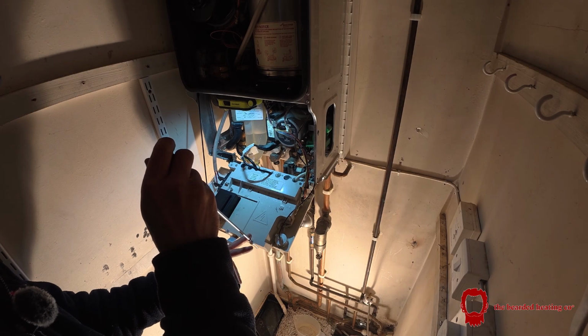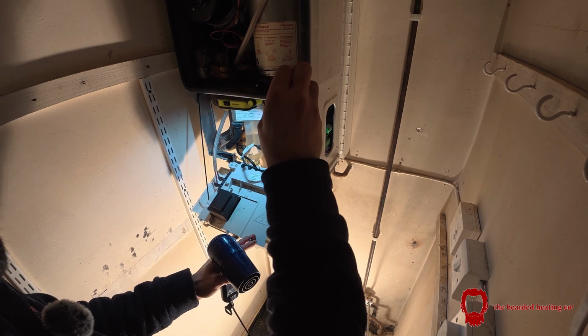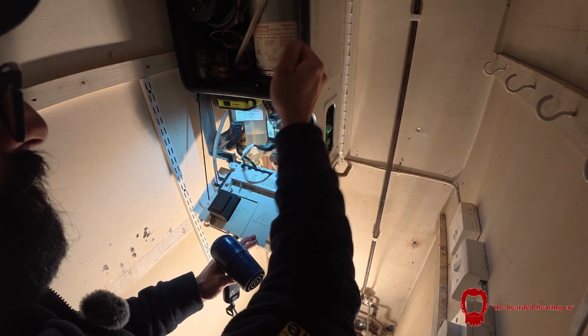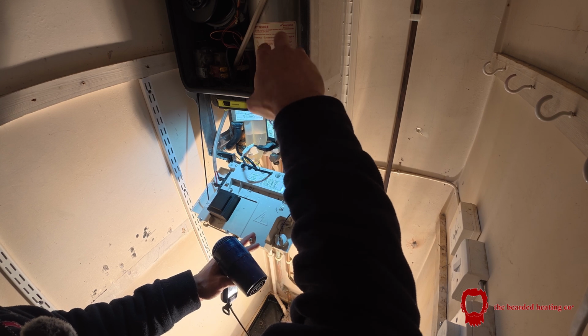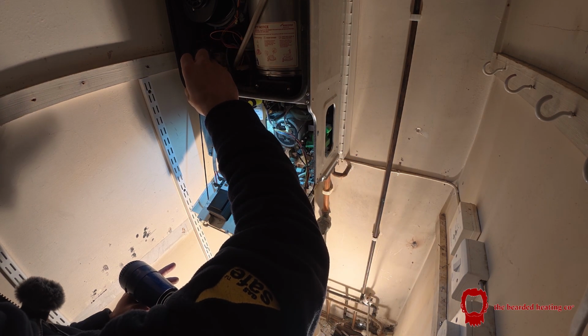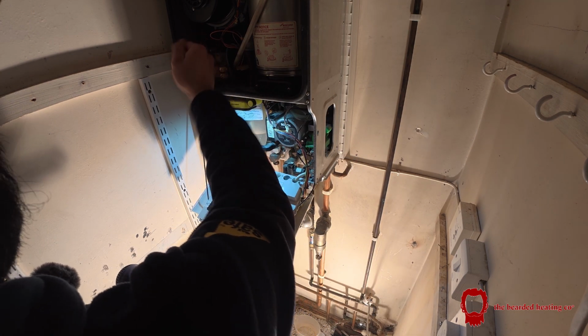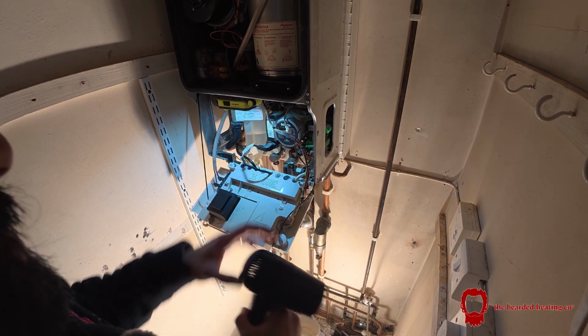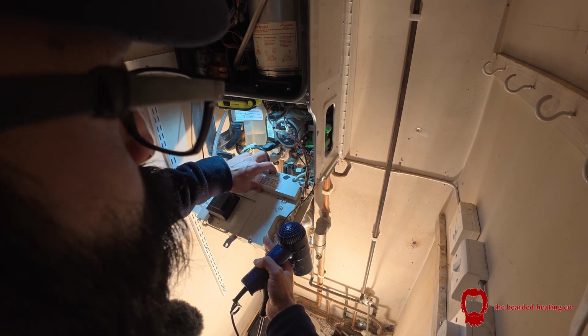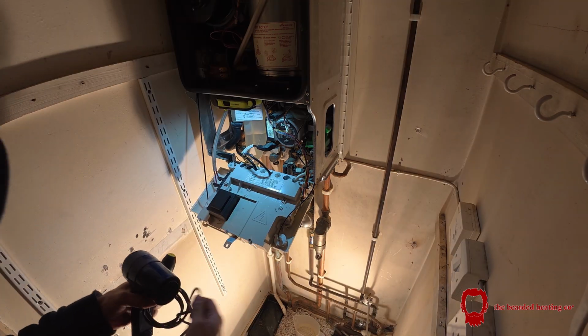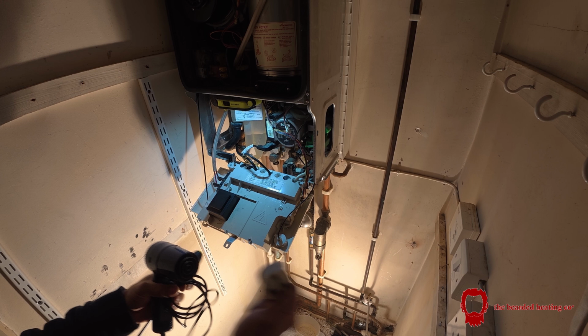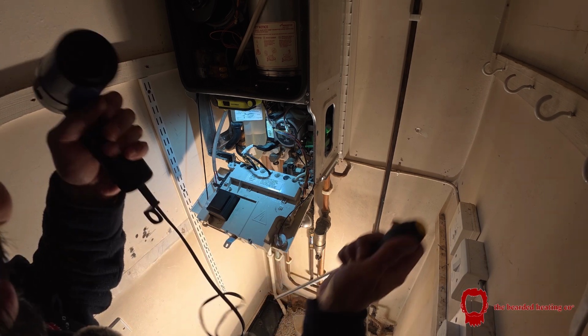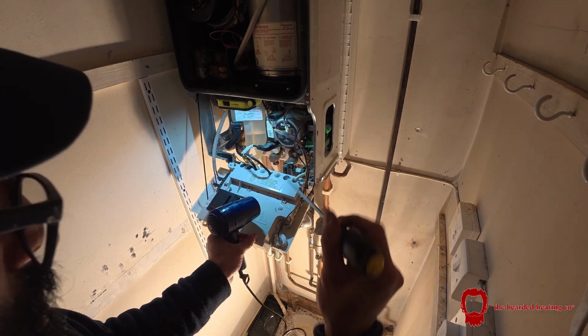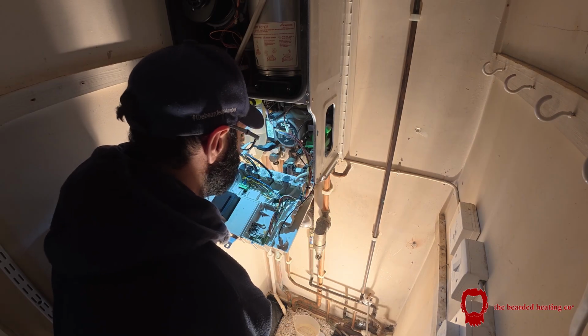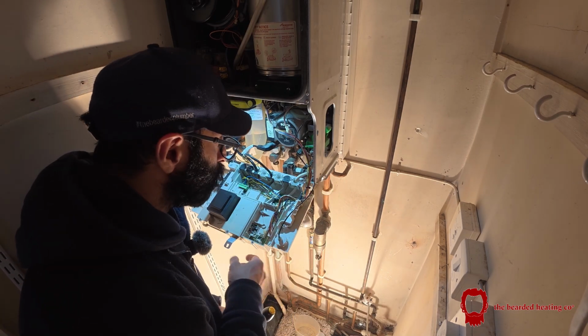So the boiler is giving me a flashing blue light, usually off, then it flashes on once every 5 seconds or so, along with the red reset light. Basically that says ignition lockout, blah blah blah, but it's not even trying to fire, and right at the bottom it says could be PCB. So as we know, the boiler is old, and this sort of turning the power off can cause the PCB to act up. Sometimes heating it up with a hairdryer can bring it back to life, so we'll give it a try. But this PCB is bone dry, I haven't got any water in it.